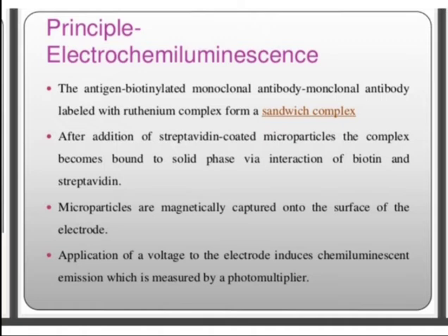Microparticles are magnetically captured onto the surface of the electrode. Means these streptavidin microparticles are magnetically captured on the surface of the electrode, and application of a voltage to the electrode induces the chemiluminescent emission, which is measured by a photomultiplier detector.